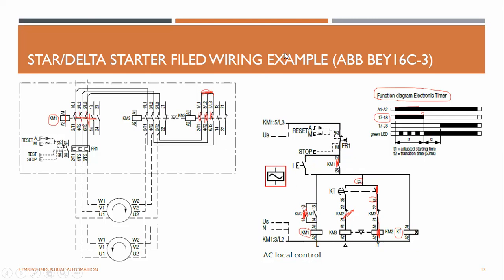flow will continue from this path through here, through self-latch KM1 coil, and here. So this guy is always turned on, and this one is opened, and this one is closed. So the star connection is happening. So after this T1 adjustable starting time, the user can adjust this T1 time for the run of the motor for the star connection.